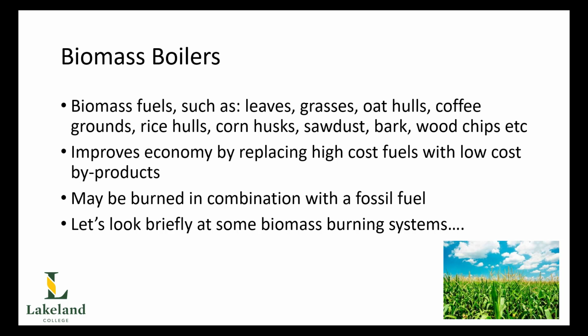Now again, biomass can be a useful tool to not only supplement our fuel, but can also massively reduce our costs of purchasing that fuel. The only real problem with biomass as a waste product is that it can often contain large amounts of moisture and has a fairly low calorific value. So a great deal of it must be burned, and it can often be seasonal, in that it's not available all year round and we have to store large amounts of it to get us through the off season. So these biomass burners are basically ways in which we can combust this material in order for it to release the heat that we need to generate our steam.